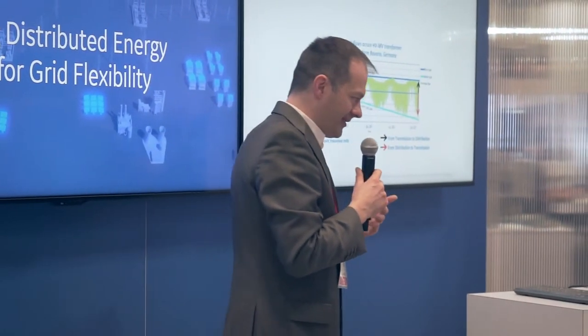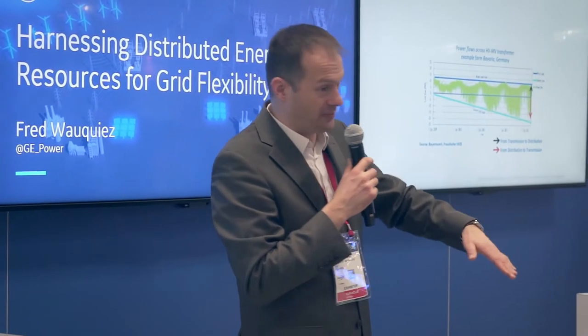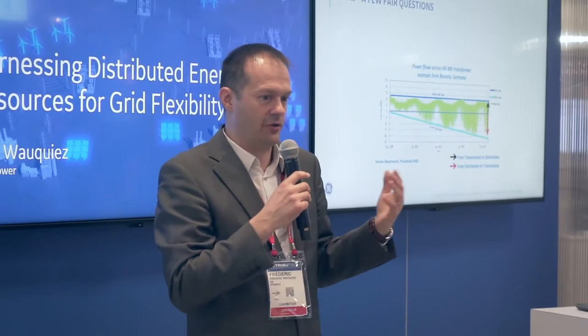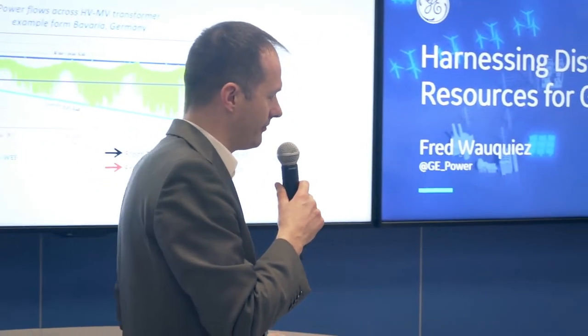Maybe you're not there yet as a utility — there isn't that much PV on your grid today. You're not Bavaria, you're not California yet. But this will come, so you'd better prepare. Preparing means knowing what happens and also all the processes and logic attached to it. You're used to running your grid knowing that voltage drops. Well, no longer — voltage drops only when there's no PV, and when there is PV, there's a voltage rise. So you have a voltage profile that's just not the regular stuff. In all your daily operator routines, you need to think differently. Do you know the impact? Do you have a sense? Do you start to see the impact in some neighborhoods, some regions, some parts of your grid?